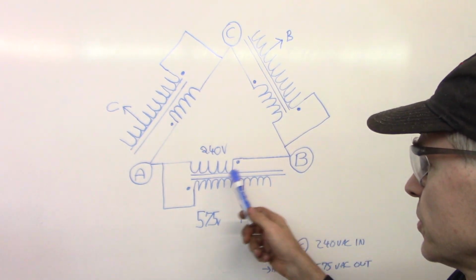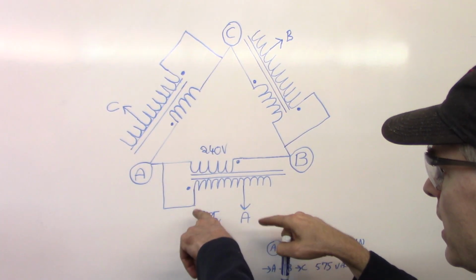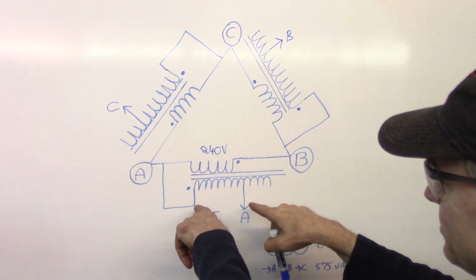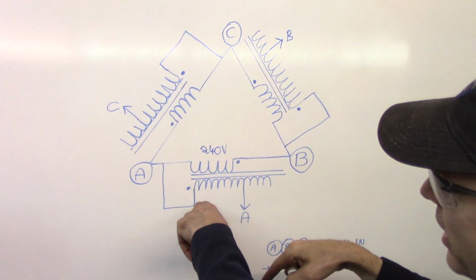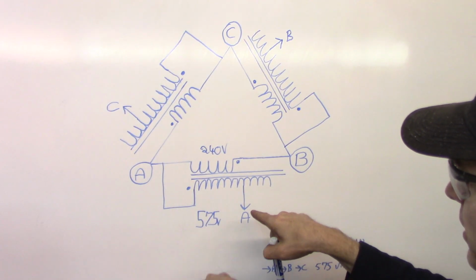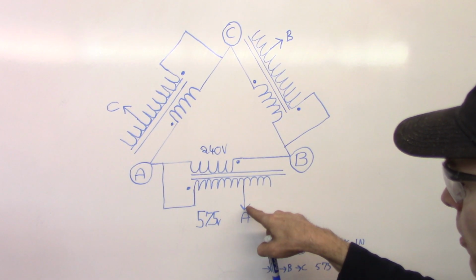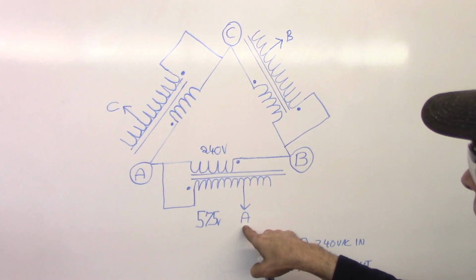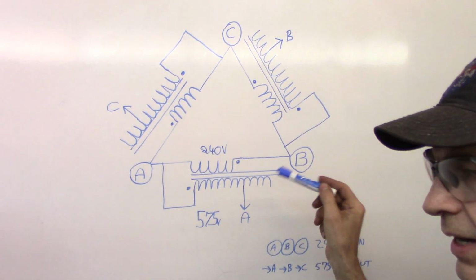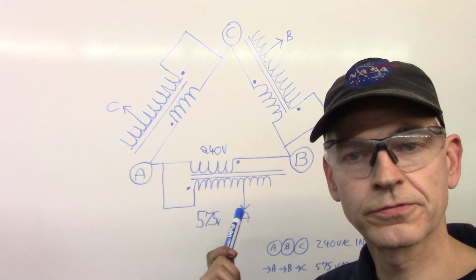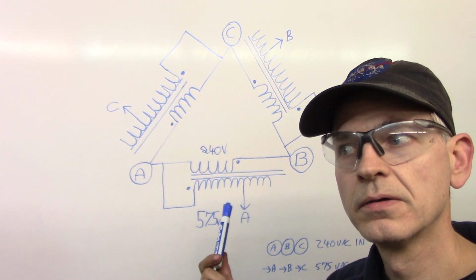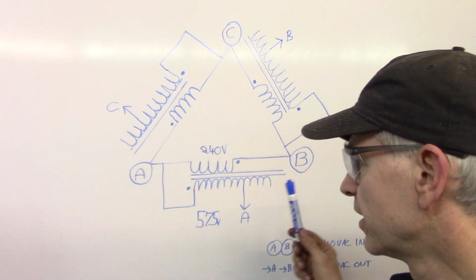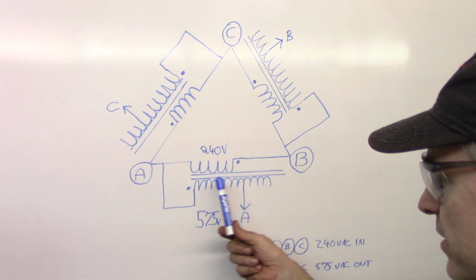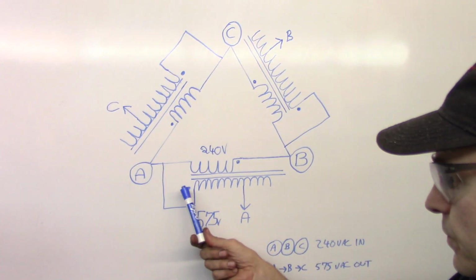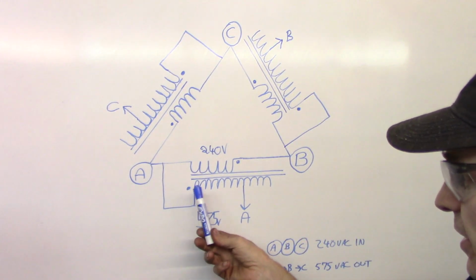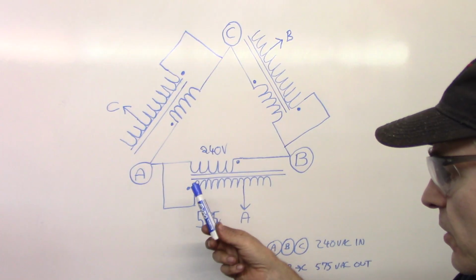But because I'm not using it, I could take my load off this side, tie all the one sides together in a delta, and your output would be arrow A as your output. I could do that, but I said I'm going to make these wired for an auto transformer, not an isolation transformer. These lines of the iron core, that's the isolation.